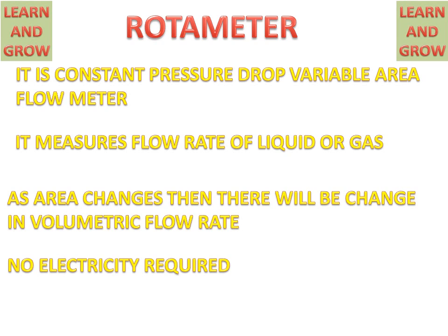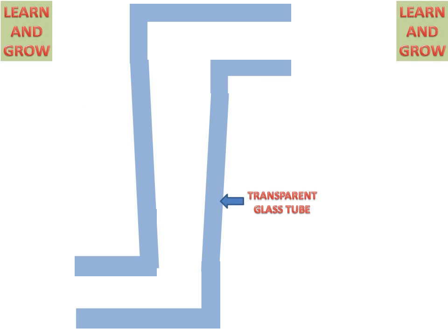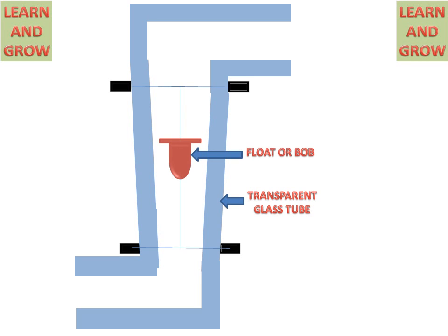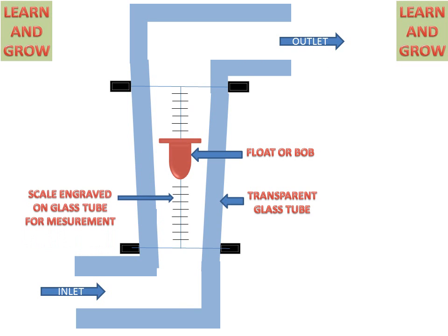We will see the working and parts of the rotameter. It has a transparent glass tube and a float or bob. The inlet is from the down side of the rotameter and the outlet is from the upper side. A scale is engraved on the glass tube for measuring the flow rate.